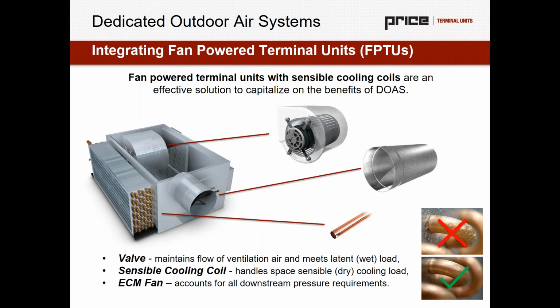And for those of you who are not familiar with series fan powered terminal units, what we're really looking at here is an offset of air volume between the fan and the primary air inlet. Because that fan is discharging air downstream and inducing air from the equipment casing, from the inlet, and from the plenum through the coil, the offset between fan and primary is going to be the volume of air we see drawn through the coil and cooled down by our elevated chilled water temperature.